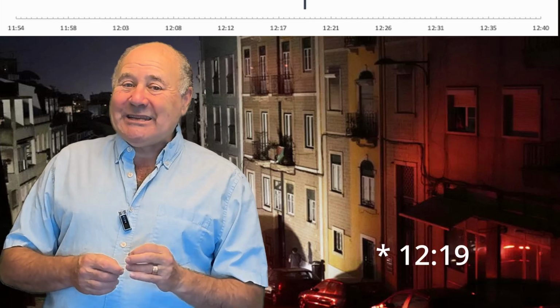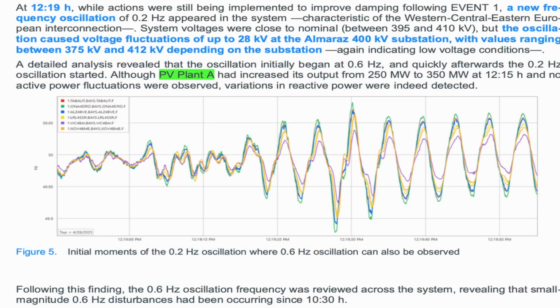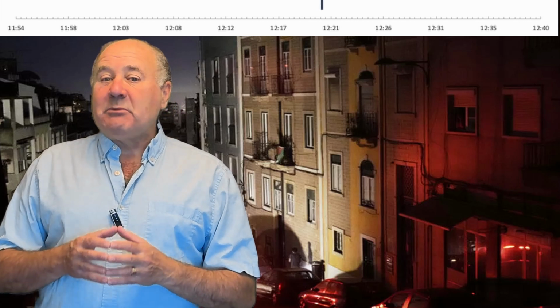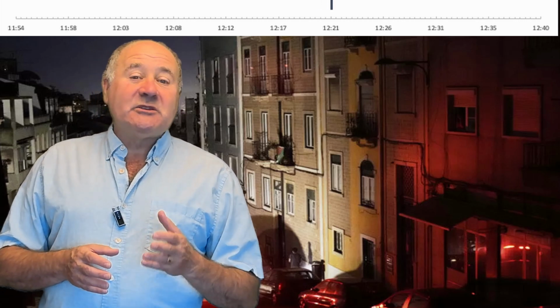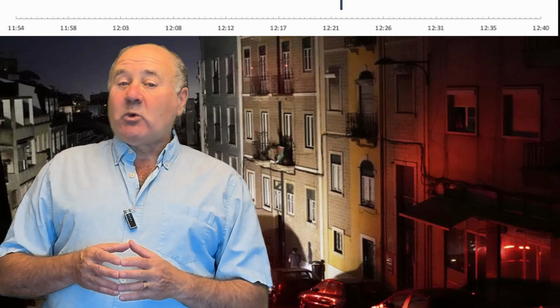By 12:19, a new oscillation at 0.2 Hertz appeared, likely coming from the European grid. The grid operator took additional measures to further dampen these oscillations, again reducing power being sent to France and Portugal and reducing system impedance. These interventions worked and the system recovered by 12:22.